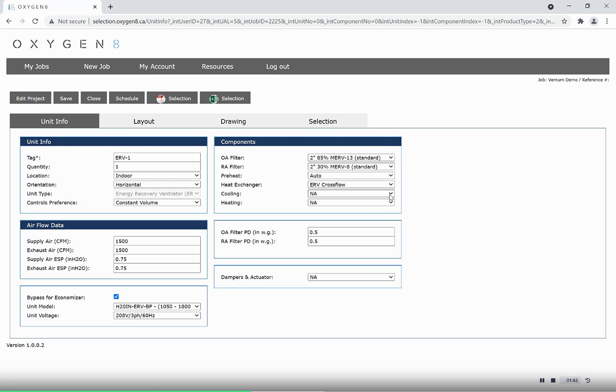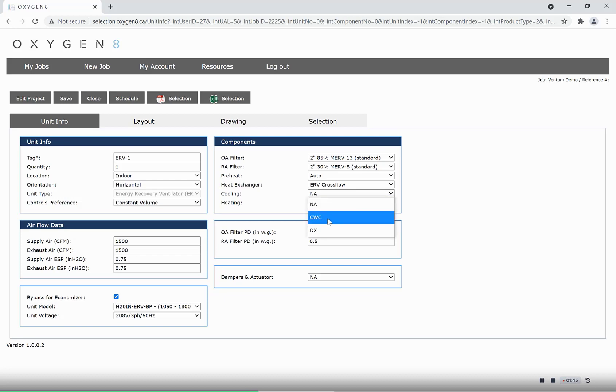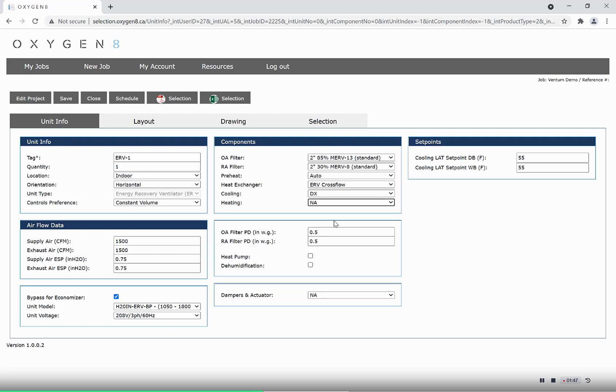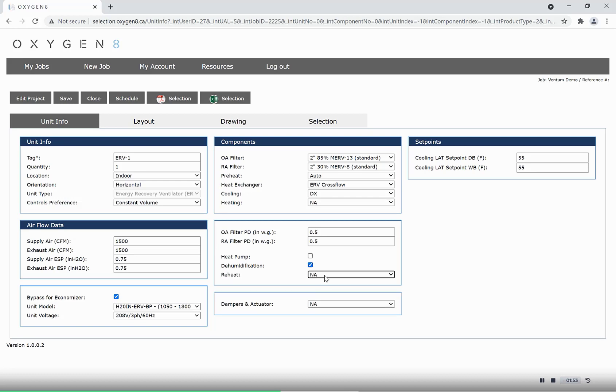On the right-hand side, heating and cooling can be added, either chilled water coil or DX. If DX is selected, there are additional options that will show up. It can be run as either a heat pump or can have reheat added to it for dehumidification applications.